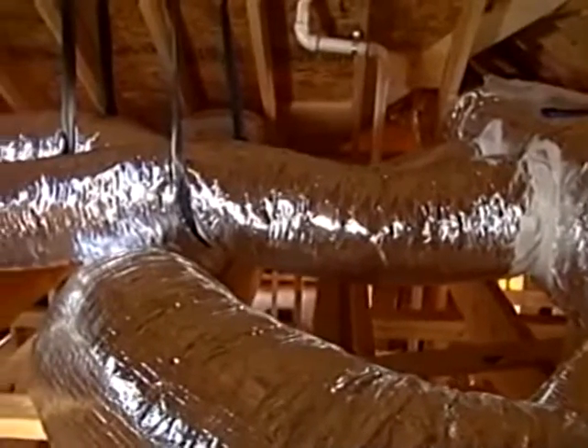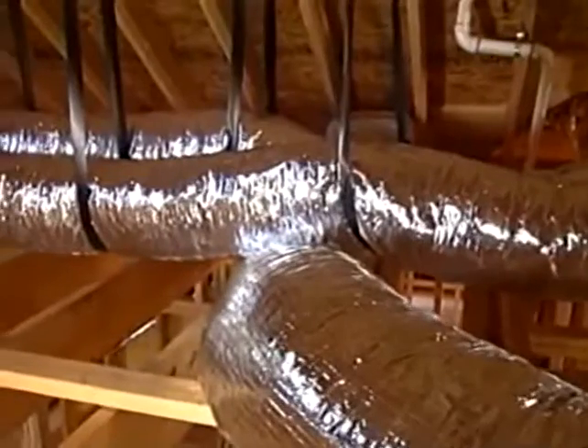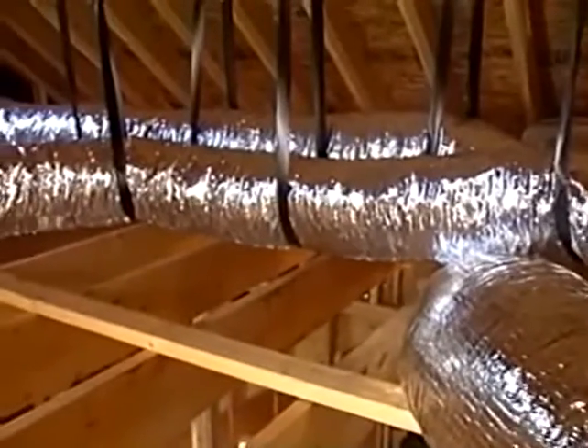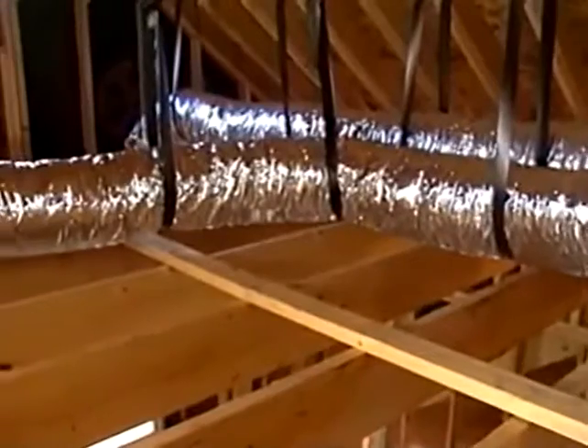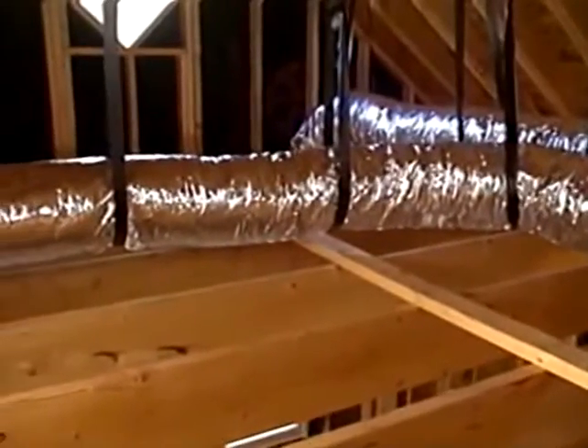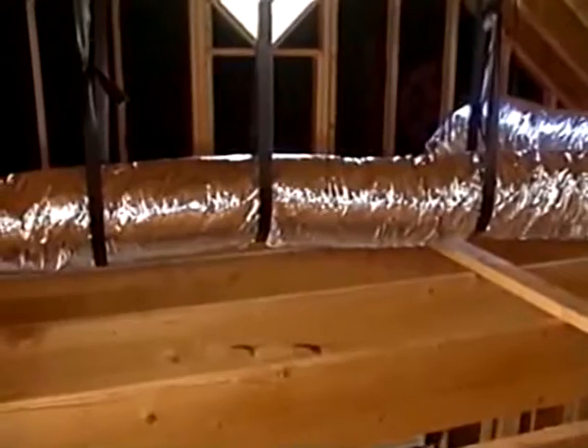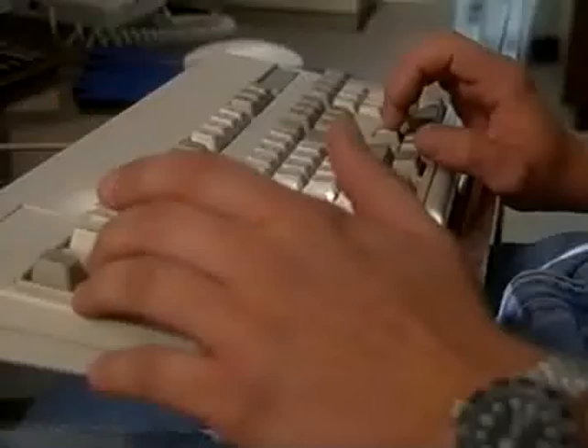A well-designed, comfortable air distribution system has straight runs and gradual turns. This layout shouldn't change if you are using flexible duct. The thing about flex duct is that it's flexible, and so that makes it really nice, you know, in that you can avoid the plumber, you can snake it around. And I hear people use that term. I cringe every time I hear somebody say, well, you can just, you know, snake it from here to there. You need to run ductwork like it's already ductwork. That's the way it carries air around. So because flex is flexible, sometimes it is a disadvantage instead of an advantage.